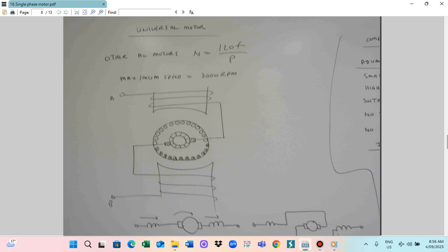Speed N is equal to 120 F divided by P. It follows the equation: the number of poles and the frequency. So the maximum speed you can get is 3000 RPM, because to run a motor it needs at least 2 poles. In this case, the maximum speed can be 3000 RPM.